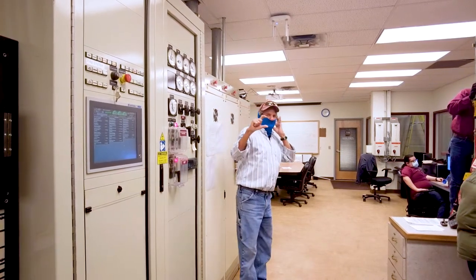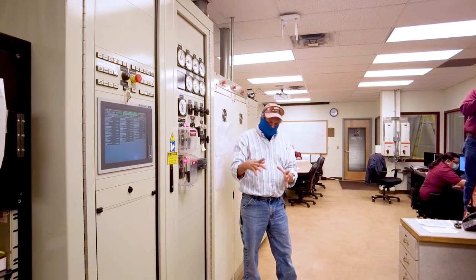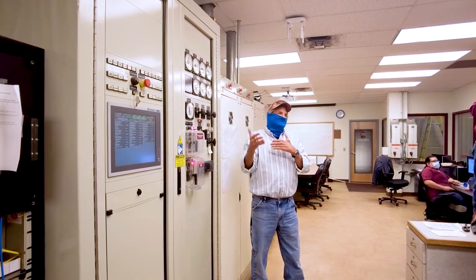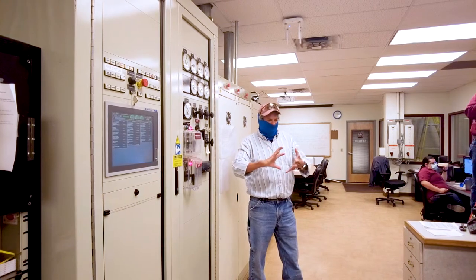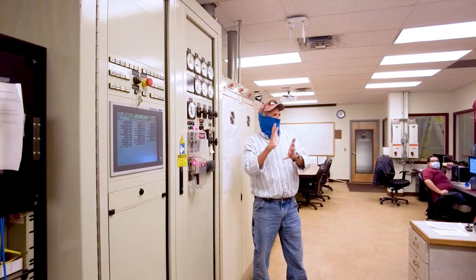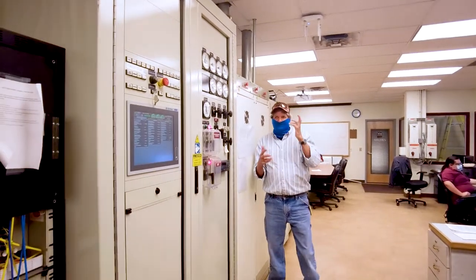I have a piece of a shaft from a hydroelectric dam, a 10 megawatt hydroelectric dam. It's about that big, it's about that thick, and it weighs about 50 pounds. And you can see where they never synced it in, ever, when they were turning it on. You can see all the little imperfections in that shaft. And you can also see where it cracked a number of times before it finally broke in half. It's very interesting to see if you look at it and study it.